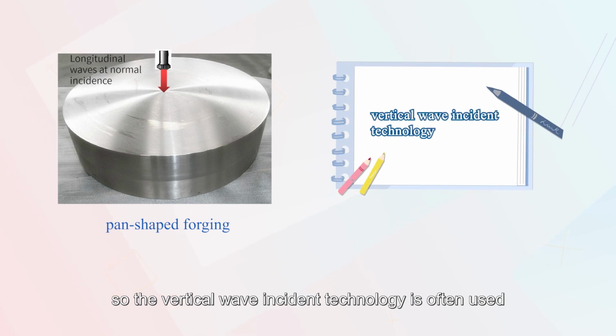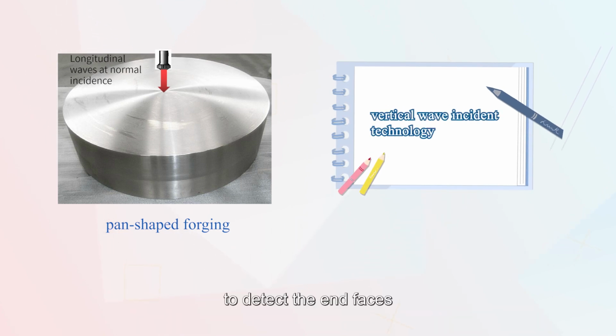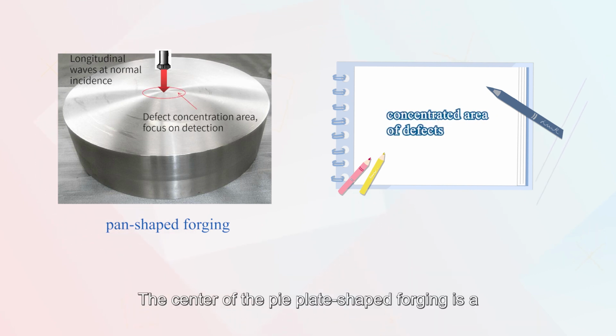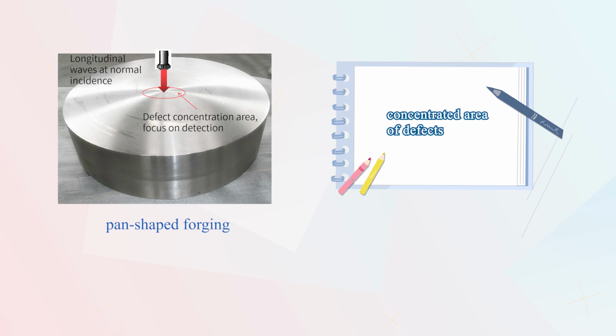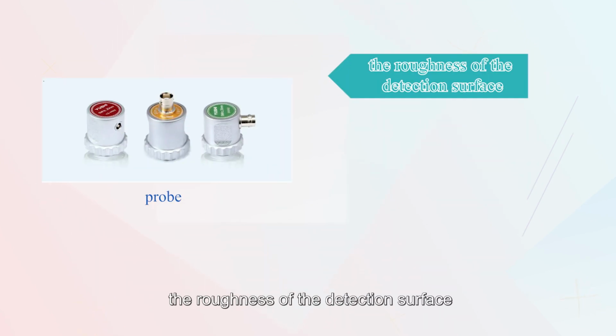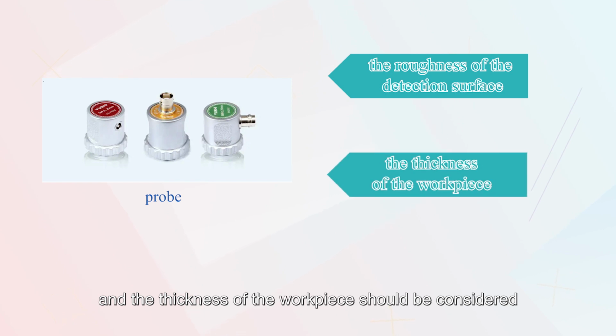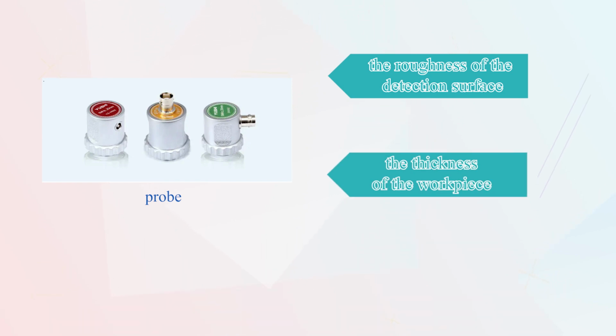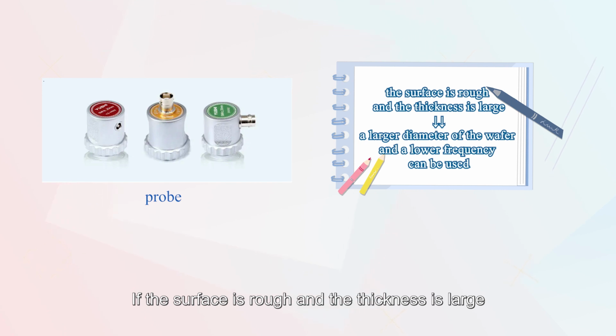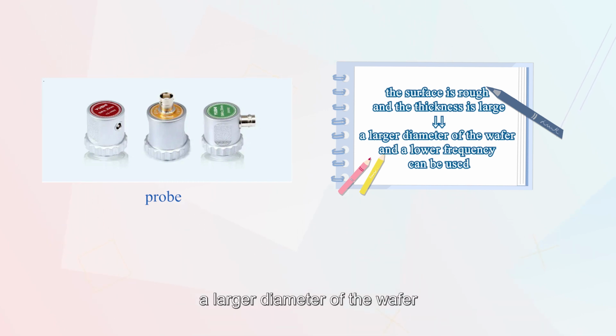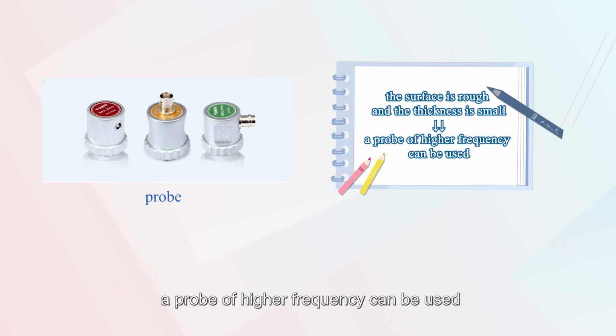So the vertical wave incident technology is often used to detect the end faces. The center of the pie plate-shaped forging is a concentrated area of defects, which needs to be inspected. When selecting the probe frequency, the roughness of the detection surface and the thickness of the workpiece should be considered. If the surface is rough and the thickness is large, in order to increase the energy of the incident acoustic wave, a larger diameter of the wafer and a lower frequency can be used. Otherwise, a probe of higher frequency can be used.